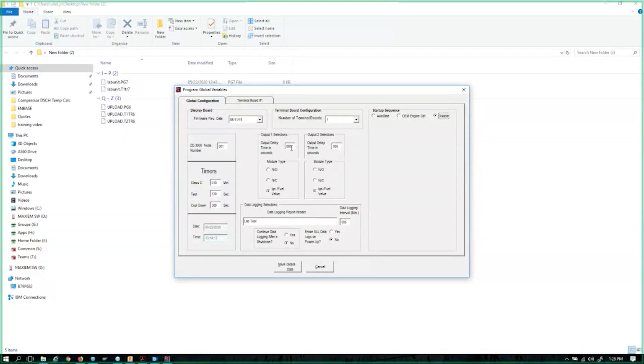So on a fault, I would want the ignition to shut off after the fuel. And that's exactly what this is indicating. So it's output delay time in seconds, and there's one little word missing from this statement here in the center of your screen. It should really read output delay time off in seconds. So this confuses a few people. Once you know this, it's imprinted in your brain and you'll never forget it, right?